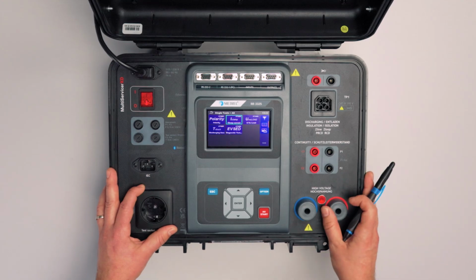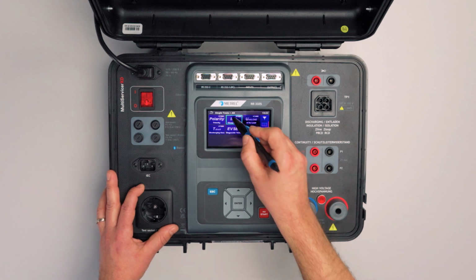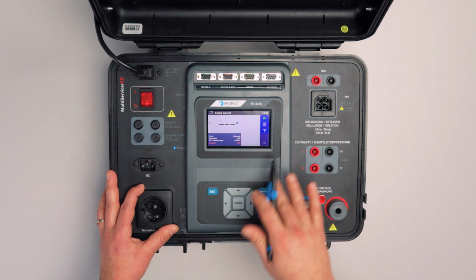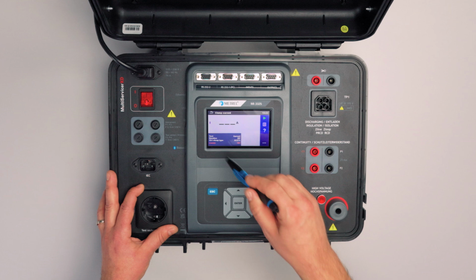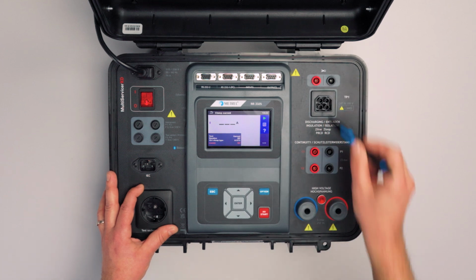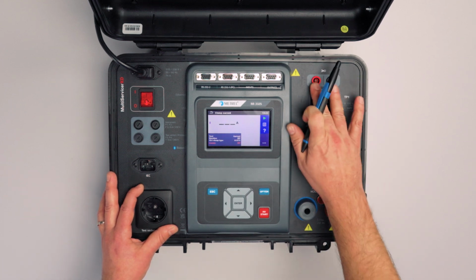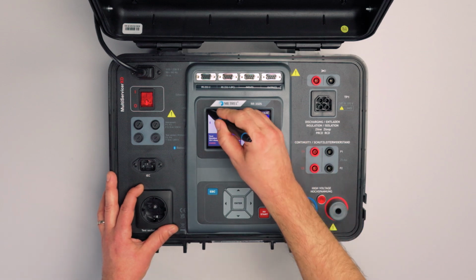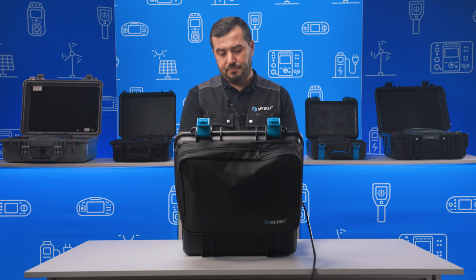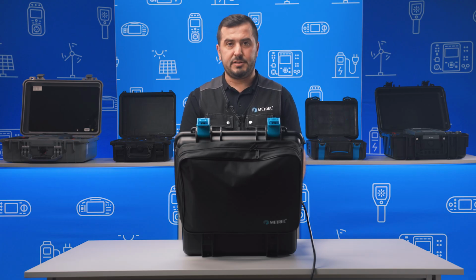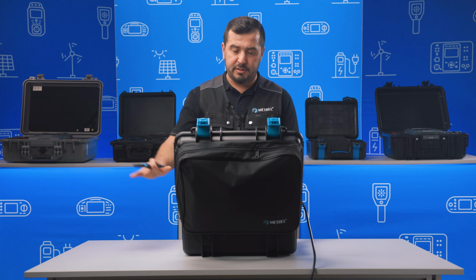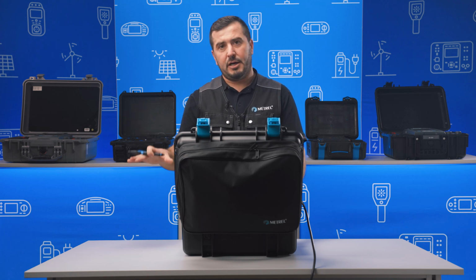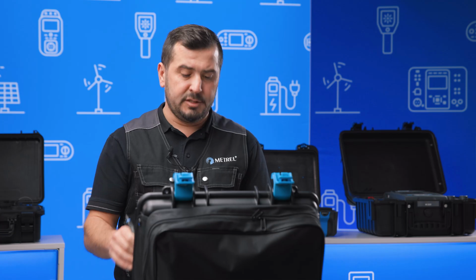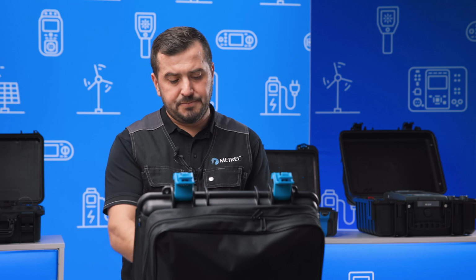The next menu is the current clamp menu, where we receive the measuring result from the optional current clamps which are connected to this test terminal. Then the no load voltage. This test is again covered only when the active three-phase adapter is connected, and in this case we have to have the A1422, which enables the testing of welding equipment.